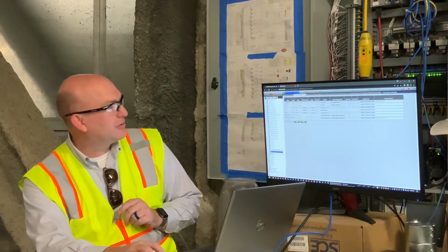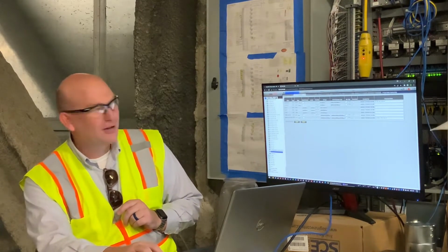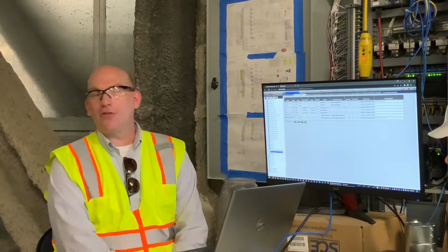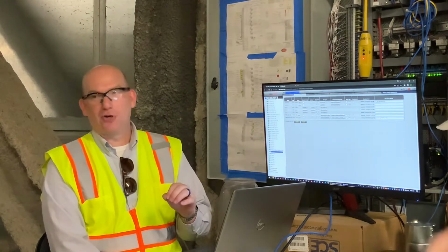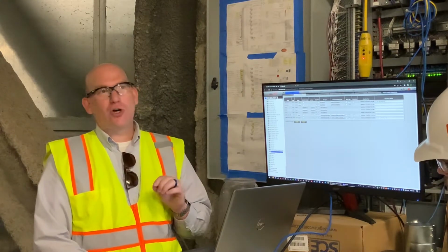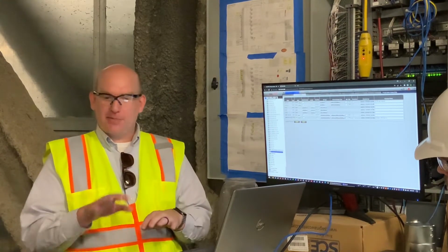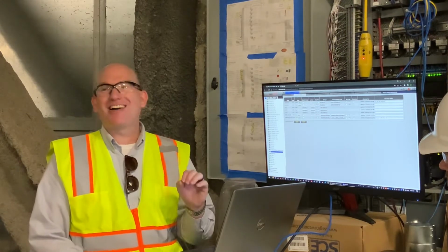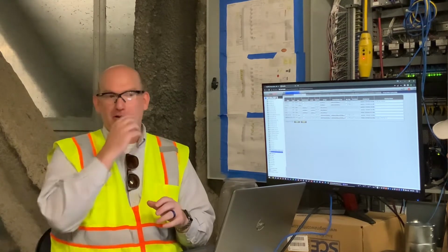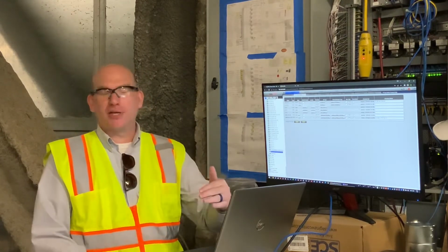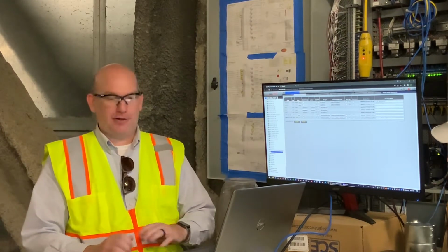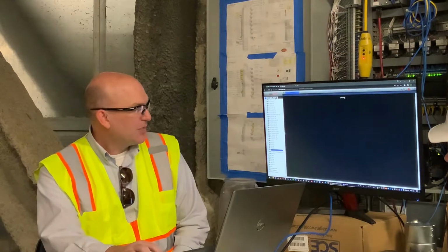So let's talk about our I/O. Are you measuring CFM? Yes. There's an Ebtron airflow station on 7 through 11, on the supply and the exhaust. Okay. So there's also a third riser besides the main supply and the main exhaust, but it's a constant volume exhaust. It does like the bathrooms, and there's no airflow station on that because it runs on a dumb fan that turns on, turns off, and it's all balanced, no modulating control, nothing, right? Totally constant.